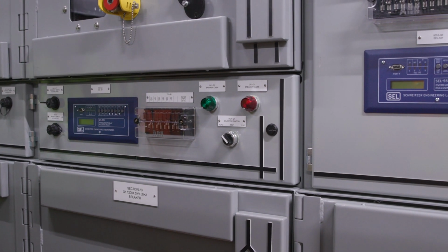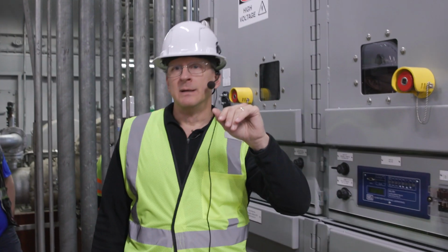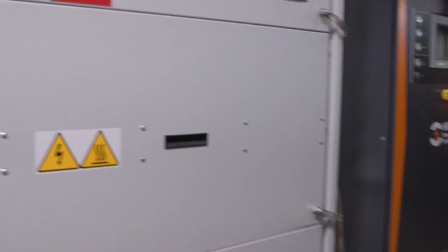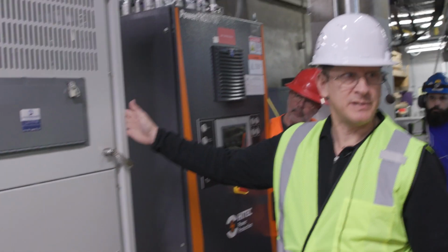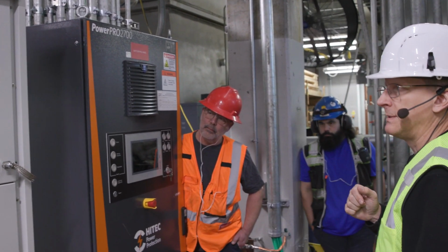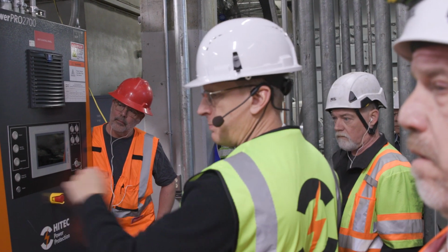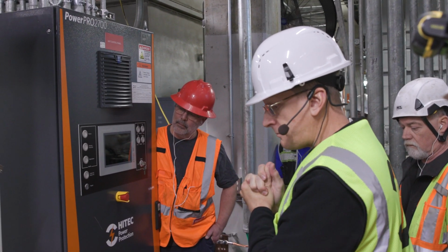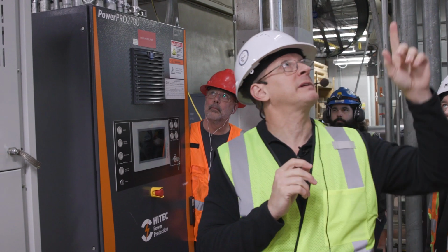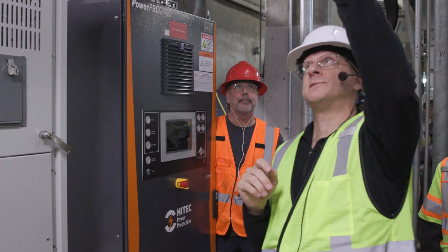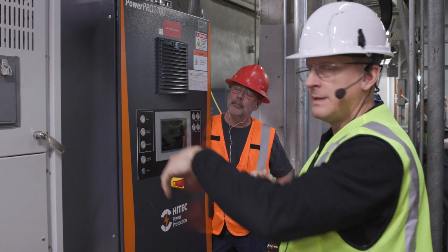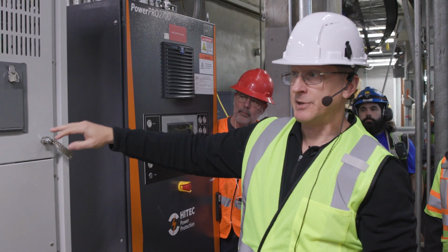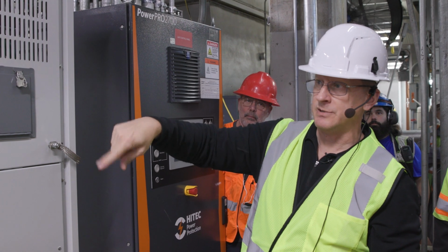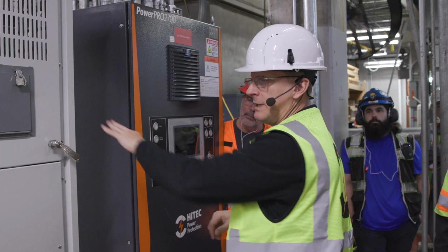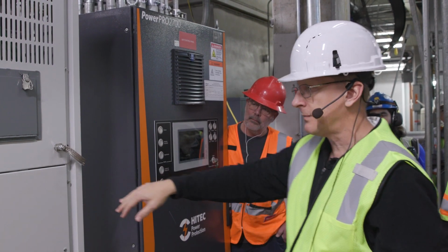Okay. So again, all this is 4160. Right here by the UCP. On the other side again, this is our choke cabinet. This contains our URP, our reactor choke. This also came from Europe as well. And you can actually follow, if you look out on top of the gear, you can see the connections into the UCP, into the URP. Again, coming from the URP Q1 and also going to the Q2 breaker. But this is where our choke sits. Again, this is medium voltage as well, 4160.